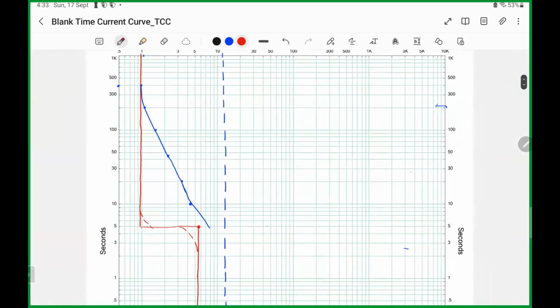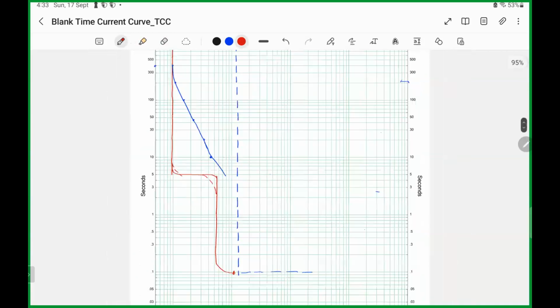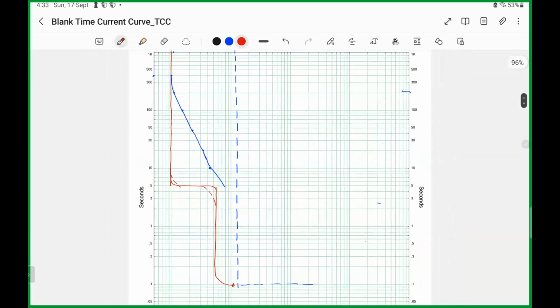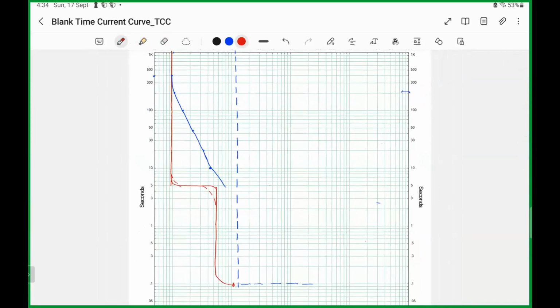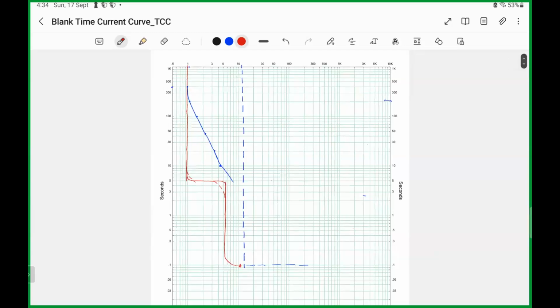As you can see here, meron tayong clearance. Okay? Kasi kung gumamit pa kayo ng small factor, definitely it will touch the accelerating time of 0.5 doon sa overload mo. So dapat merong clearance to give way to the inrush current, no, para mag-operate yung motor. Okay? Next one. So meron na tayong cable, meron na tayong motor, meron na tayong overload relay, may MCP. So next, ang i-graph natin yung low voltage circuit breaker.